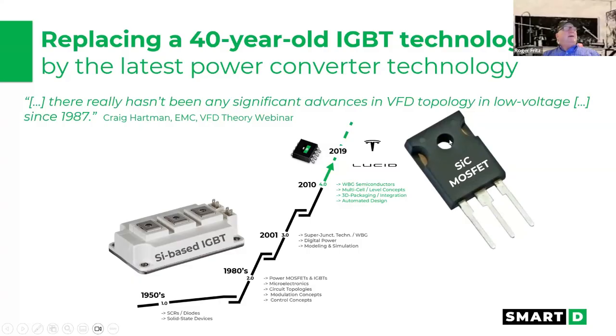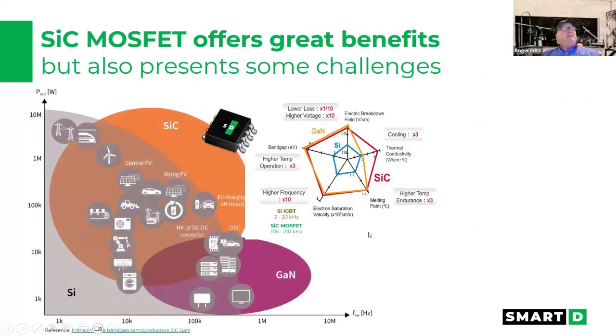And these all run at about 210 kilohertz. And the IGBT, typically the pulses are running anywhere from maybe 1.5 kilohertz to 5, I've seen 10. Some small drives are running them a little higher than that, but you still get the effect of the breakdown. And you can see that this is where they've been moving so far.